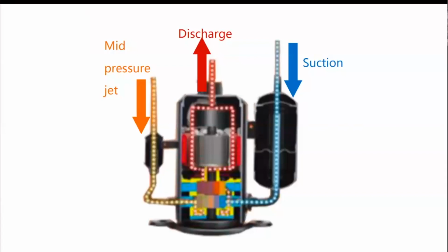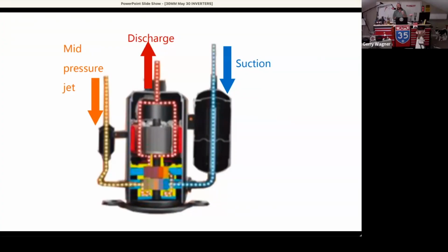Well, Doug, it's commonly called the two-stage vapor injection compressor. I always say calling your compressor vapor injection is a little bit like calling your beer fire brewed -- well, of course your beer is fire brewed, that's what brewing is. Well, of course your compressor is vapor injection, we don't compress liquid. So honestly, that's kind of a marketing term. But the key is what's significant in the title is the two-stage. If you look at the compressor on the screen right now, two suction ports -- that should be blowing everybody's mind. You've never seen that before. A single discharge, but two separate suction ports. And that's the key to vapor injection.